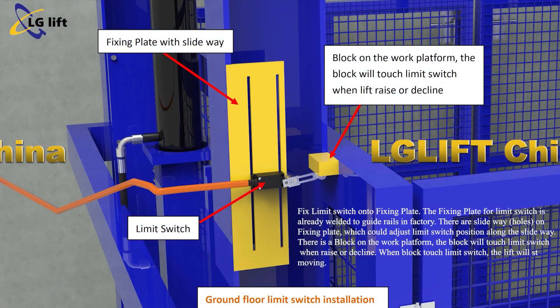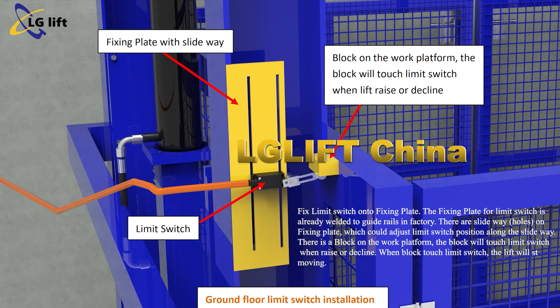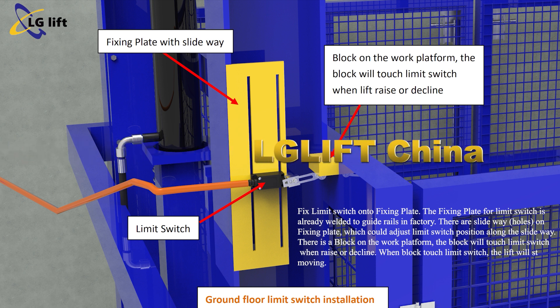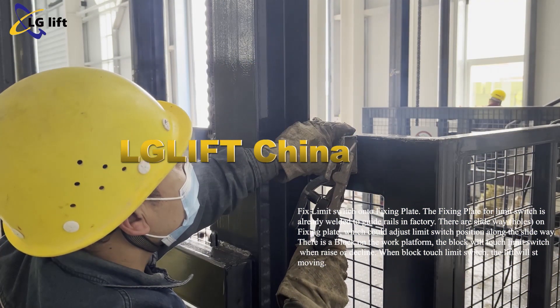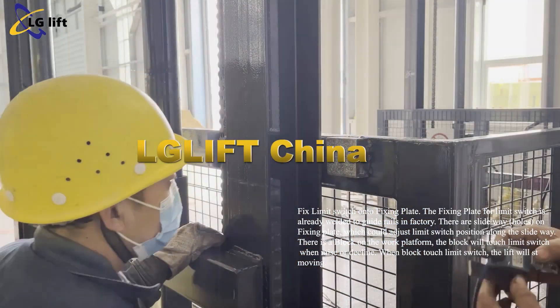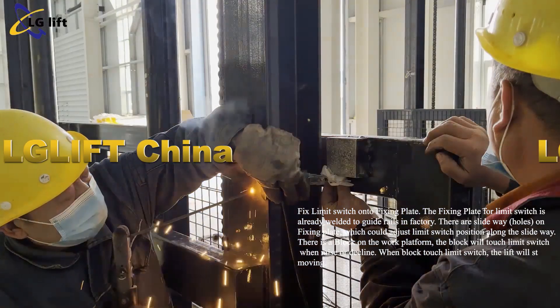Fix the limit switch onto the fixing plate. The fixing plate for the limit switch is already welded to the guide rails in the factory. There are slideway holes on the fixing plate which can adjust the limit switch position along the slideway. There is a block on the work platform — the block will touch the limit switch when the platform raises or declines. When the block touches the limit switch, the lift will stop moving.